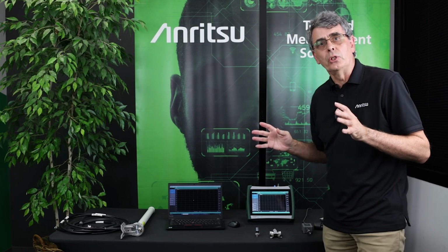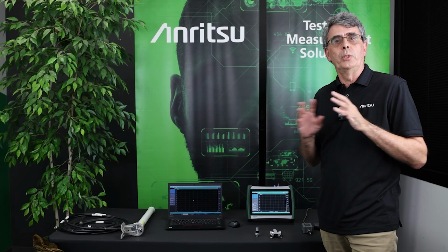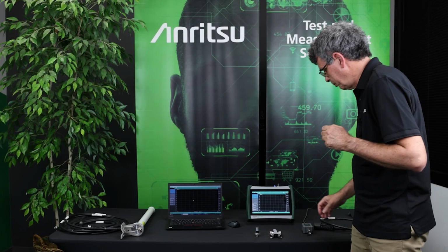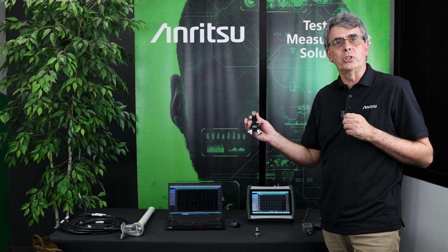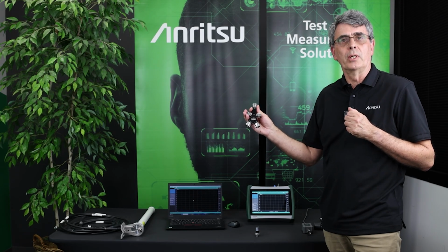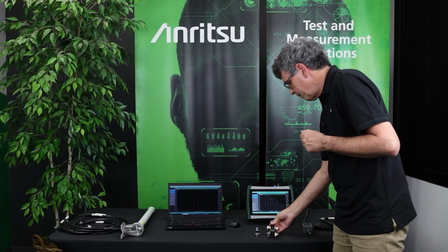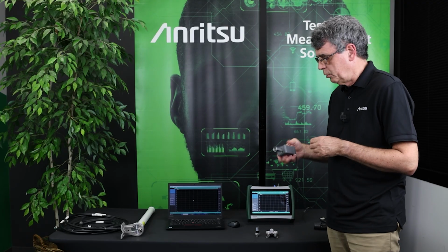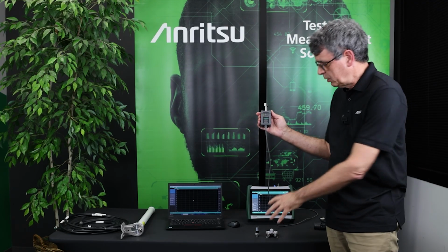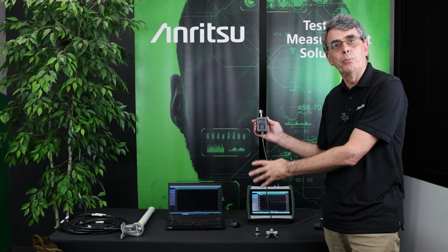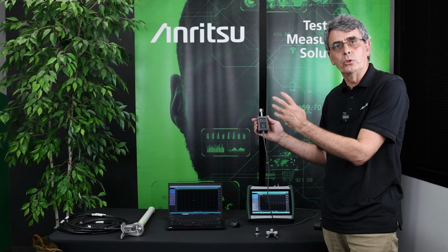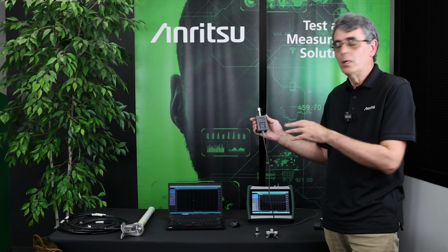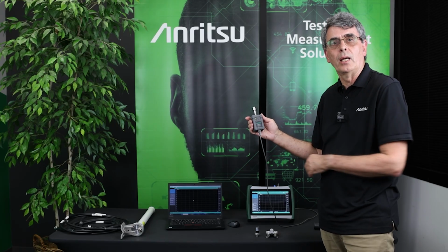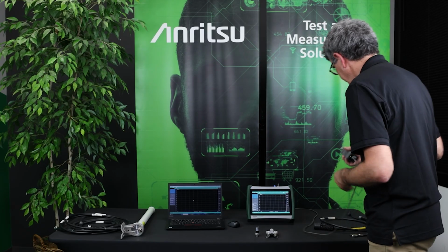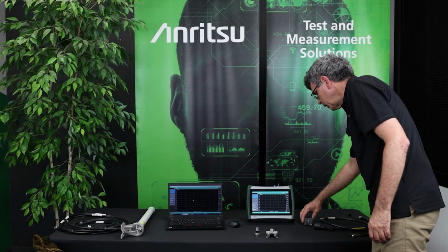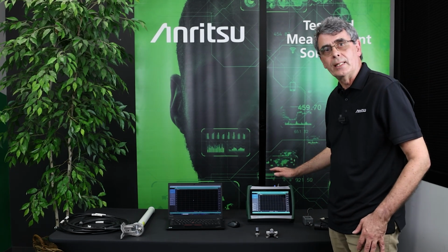The first option is to use the factory calibration data, which we call ReadyCal. The second option is to use the traditional and familiar open short load mechanical calibration piece. And the third option is to use an InstaCal module, which effectively integrates an open, a short and a load into a single module with a switch in front of them that is controlled by a USB cable from the instrument itself. So let's have a look at the first of those options, which is the ReadyCal.